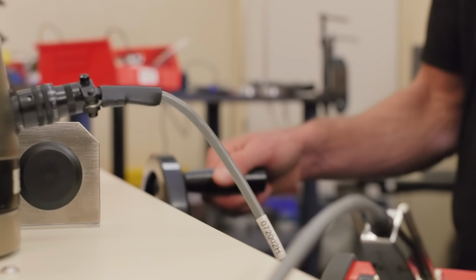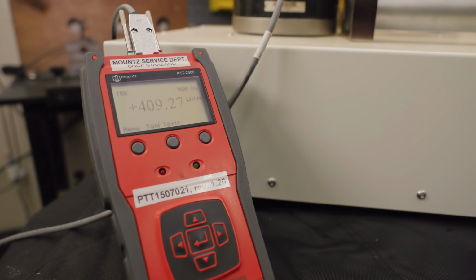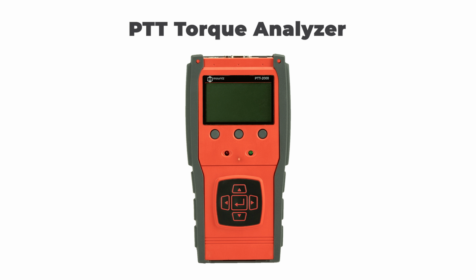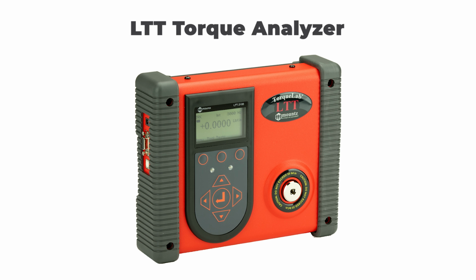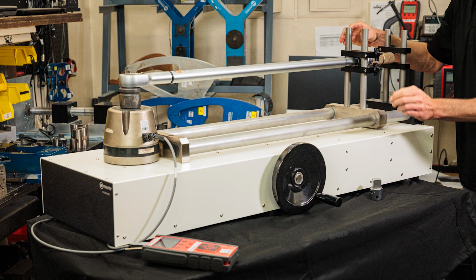Connect the torque analyzer to the sensor cable, then power on the analyzer. If using the PTT, ensure batteries are charged or use the power adapter. For the LTT, connect it to your workstation as needed. Now you're ready to begin calibration.